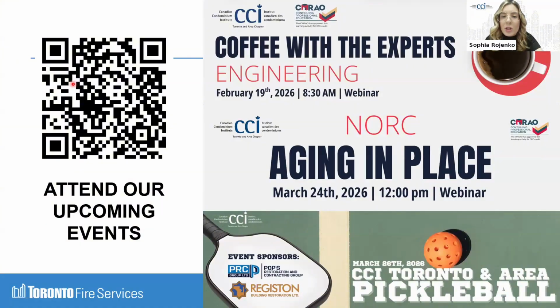All right, the next question is, the wording regarding sliding doors says that they must be tested, not checked. And as such, I believe a record of the test must be maintained. Am I wrong? If it says test, you need to keep a record of it. So your revolving door and your sliding door, you need to keep a record of that. I don't see any requirement to keep records of checking the new requirements to check your egress doors. Unless it otherwise says so, you do not need to keep a record of checks or inspections, but pay close attention to that.